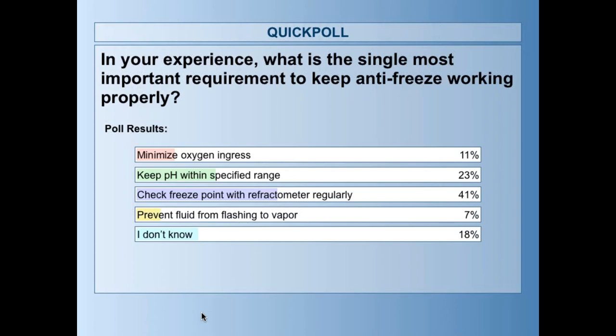So we talked about the refractometer for your freeze protection, and then the other thing that breaks down glycol, probably the biggest thing we're concerned with, is when you use it in solar thermal systems. The temperature in those collectors can exceed 344 degrees F on an 85 degree day. We don't want to flash that to steam, because we'll overheat the glycol and break it down. Again, that will typically show up in a pH number also. So yeah, that's good.